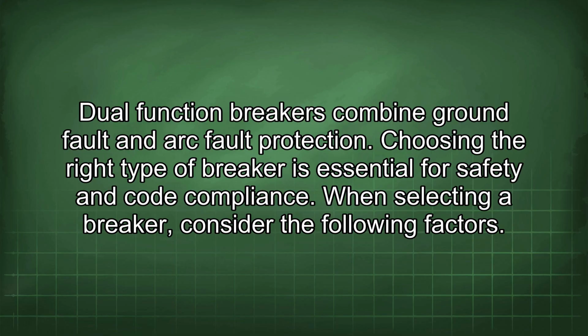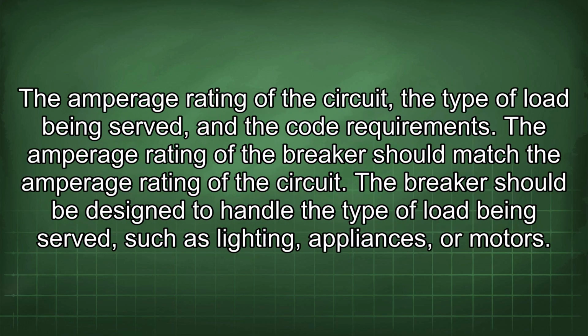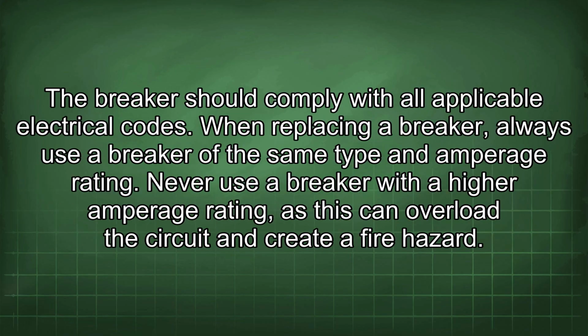When selecting a breaker, consider the following factors: the amperage rating of the circuit, the type of load being served, and the code requirements. The amperage rating of the breaker should match the amperage rating of the circuit. The breaker should be designed to handle the type of load being served, such as lighting, appliances, or motors. The breaker should comply with all applicable electrical codes. When replacing a breaker, always use a breaker of the same type and amperage rating. Never use a breaker with a higher amperage rating, as this can overload the circuit and create a fire hazard.